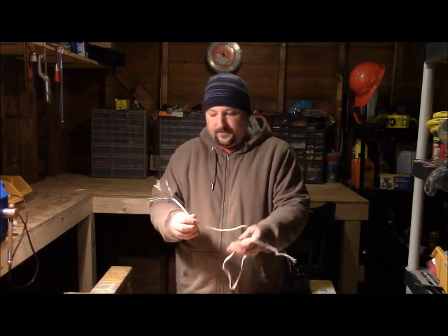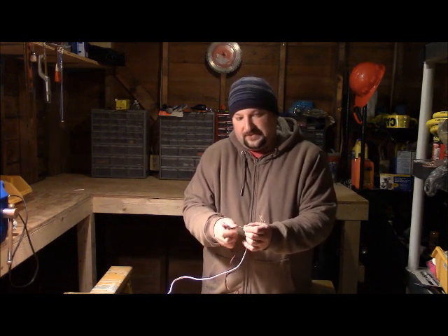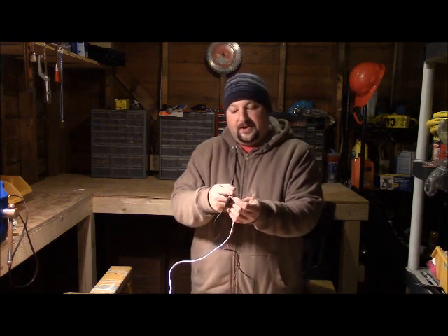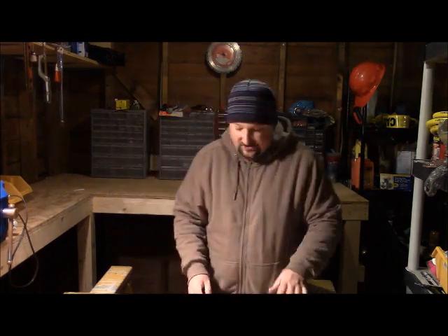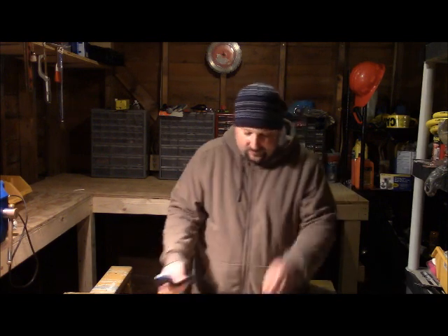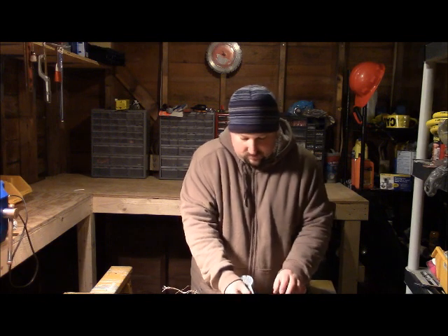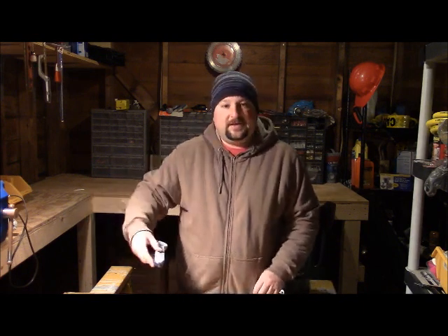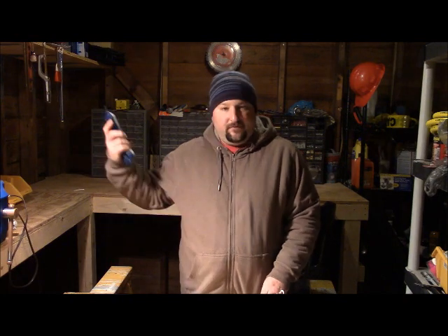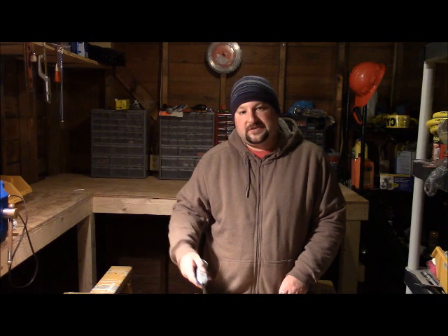I've got just a short piece of phone cable here and we're going to attach this to one of the pairs of wires. They refer to these as twisted pairs — the blue and the white-blue wires are twisted together down the line. There are four color codes in here, each one an individual twisted pair bound by the jacket. We attach to the blue pair, the tone is on, and you can see as you come down the line, as the ends come out, it dies off.